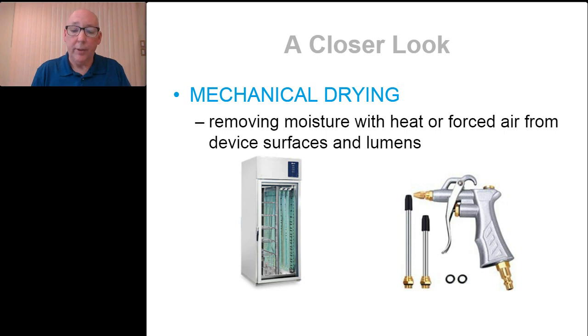Because it's a manual process, remember that? And depending on the device, you may not be able to attach it securely. So when you place that air gun compressor on a device, it's 100% manual. And if you don't place it on there correctly, you may not be able to blow all that water out of there. And certainly it's not going to just dry if it's a lumen device, again, just waiting for conductive drying to take over. Also, even though it provides a burst of air, it's not consistent or constant. It's just a burst of air, and it will not thoroughly dry the lumens that are inside those devices. Air movement works best when it's constant, consistent, warmed, and at the right pressure. And pressure is another thing to consider when using compressed air on lumens, to make sure that you're using the pressure that's rated for that device itself.